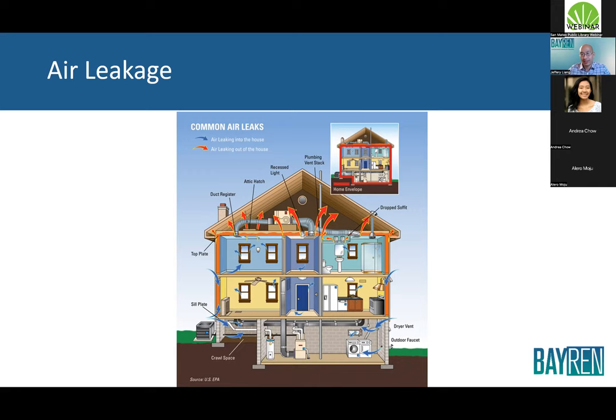Other places to look: hold your hand next to electric outlets on exterior walls and you'll often feel a literal breeze. You can actually test how much a house leaks by blowing air into the house and seeing how fast the pressure balances — when you do that, you can hold your hand next to that outlet and feel the breeze coming in or out of the house. Look at the presentation afterward for a full list of places to check.